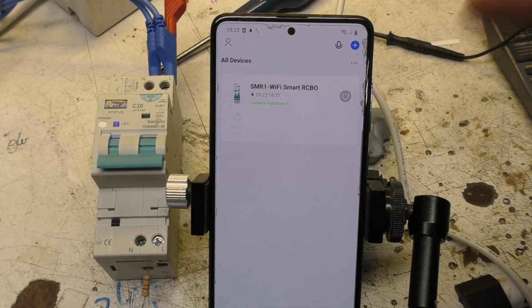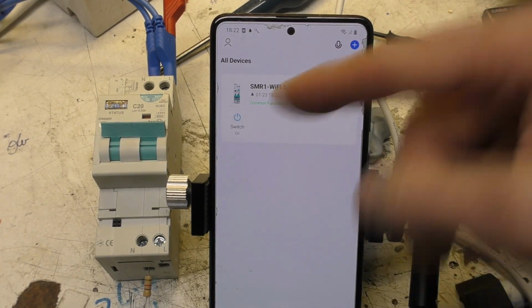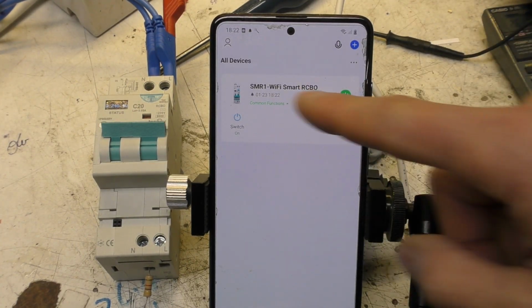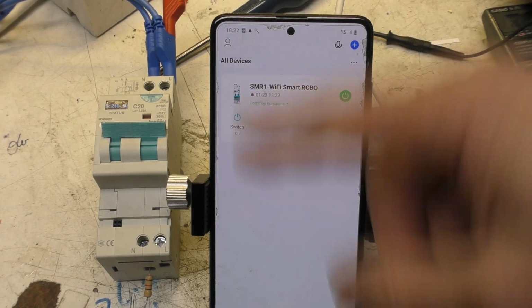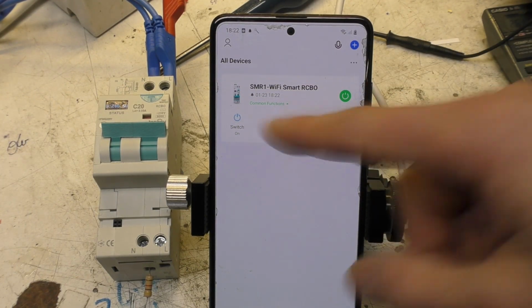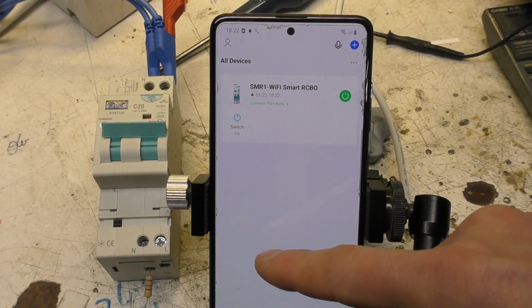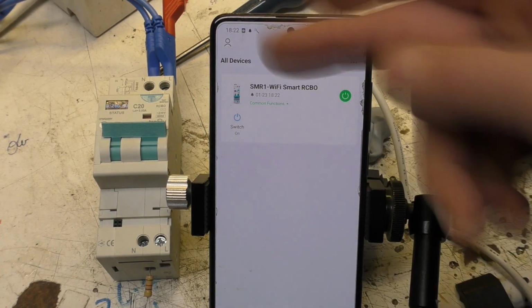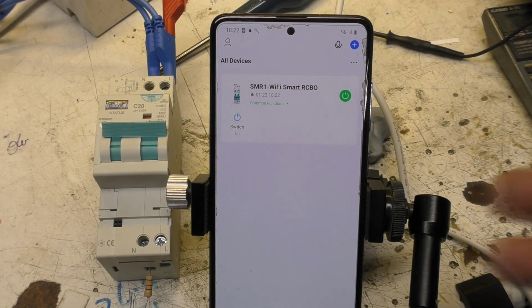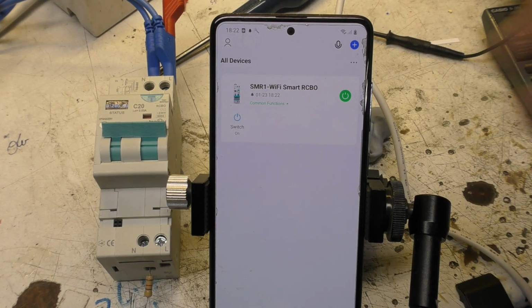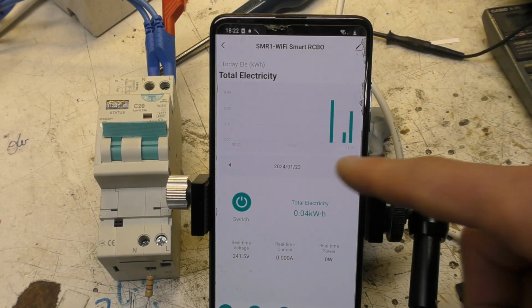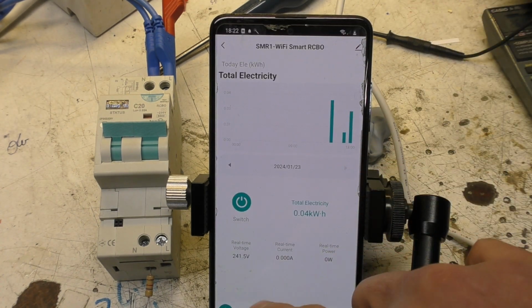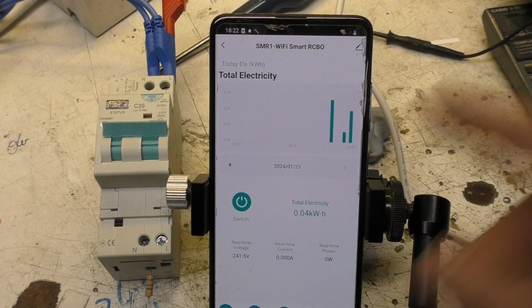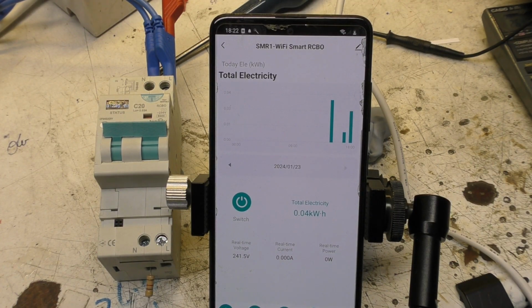Let's just take a quick run around the other functions of this app. That never gets old. There doesn't seem to be any way of assigning names to these, because obviously if you had lots of these, it'd be good to have some text description of which circuit it controls stored in the unit. There's that ID value, but even that I can't see any way of actually accessing. We've got things like total electricity usage, real-time voltage, current and power. No real-time earth leakage, which could potentially be useful in a fault-finding situation.